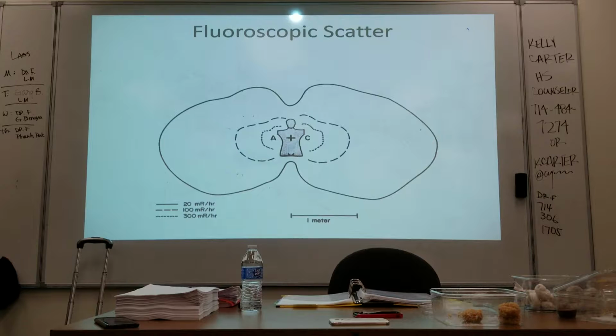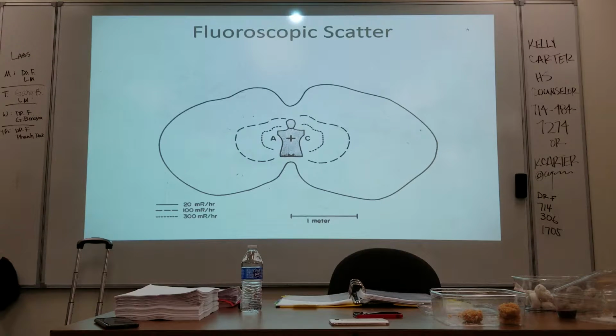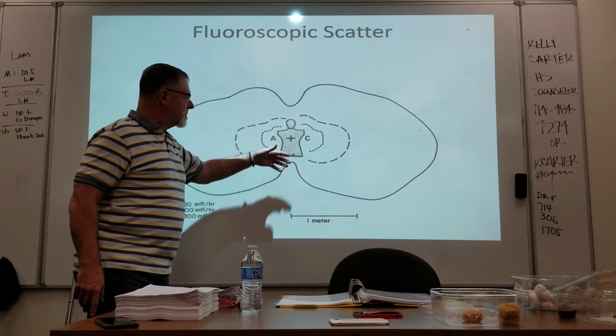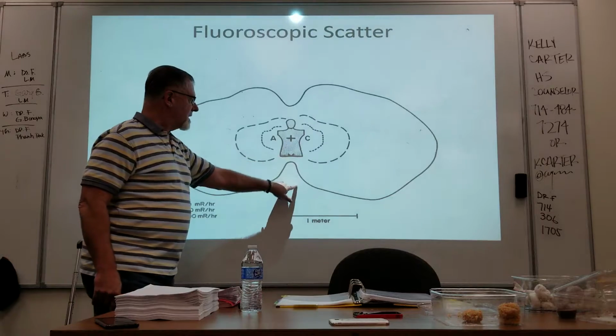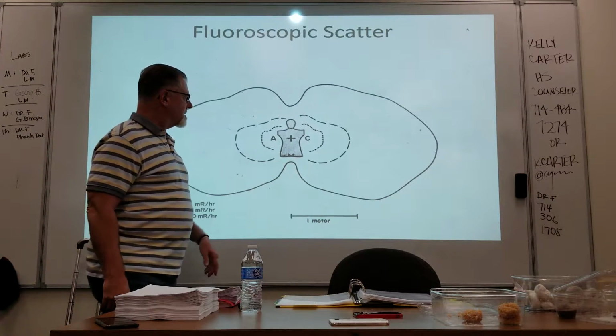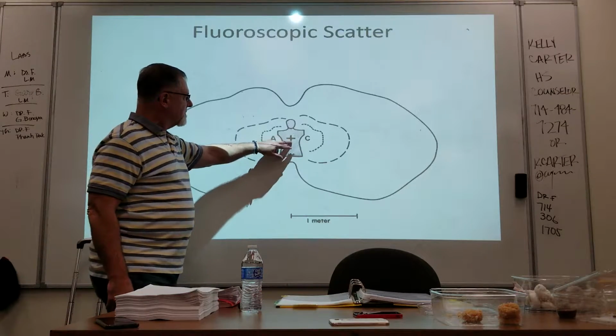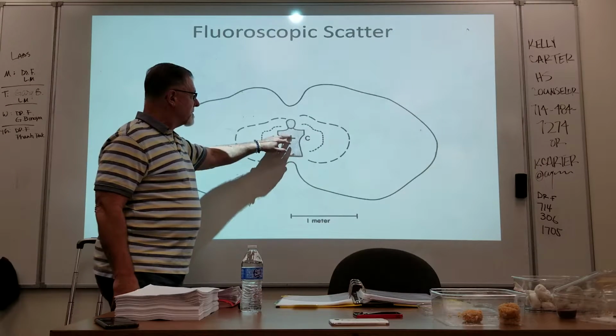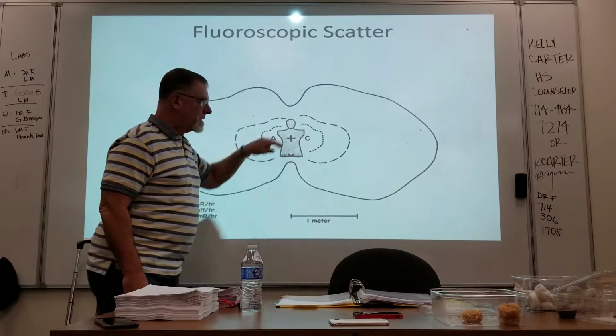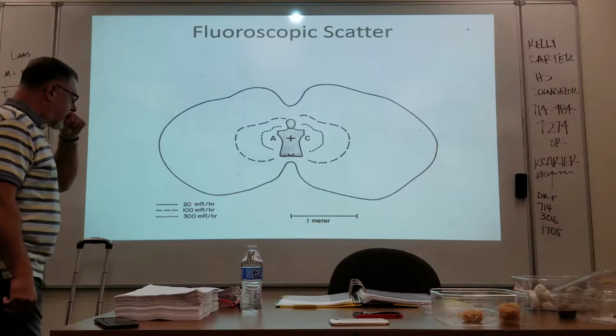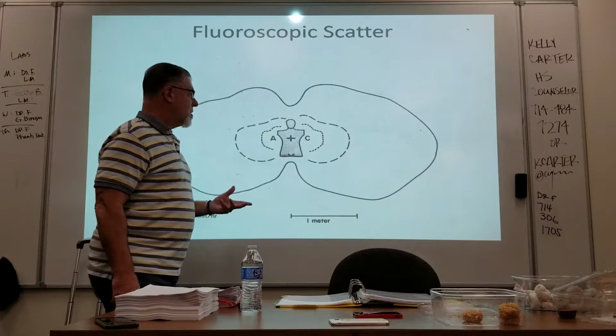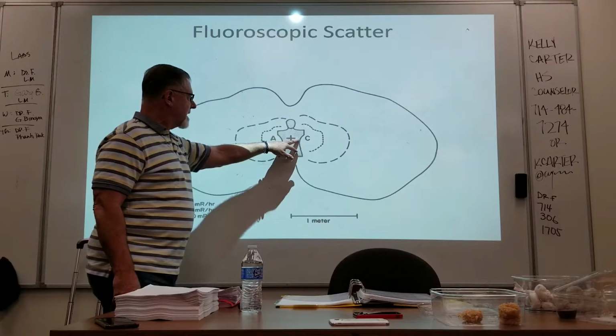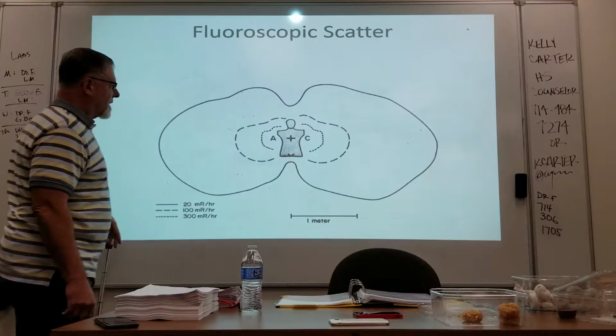Okay, so we talked about all sorts of different fluoroscopic scatter. I think the thing to remember is you have to just consider how much attenuator is between you and the beam. So in this case, this is a torso phantom. If it was a human, even with the legs, I don't know that it would do too much to change this. So you've got most of your attenuation from the mid-chest to the bottom of the torso, top of the head. So that's what these big dips are, because there's a lot of material there attenuating that scatter. However, on this phantom, which is fairly small, you have very little attenuator side to side, so you get these what I call butterfly wings.